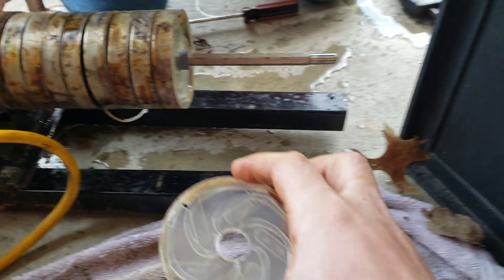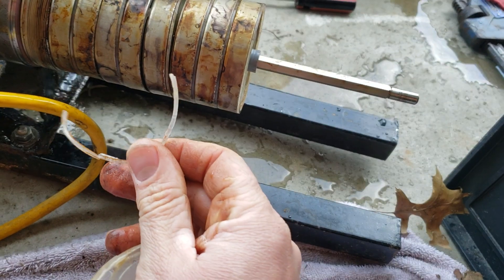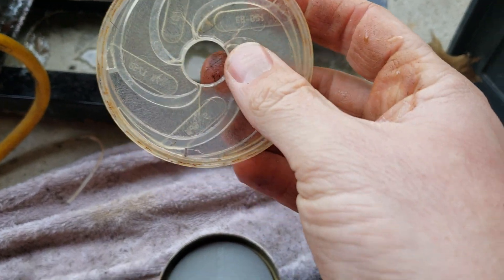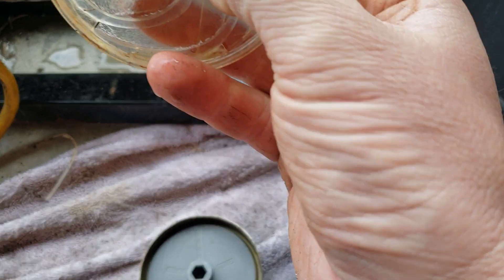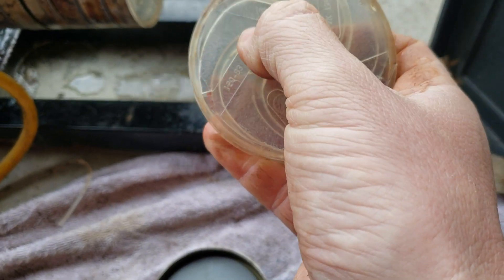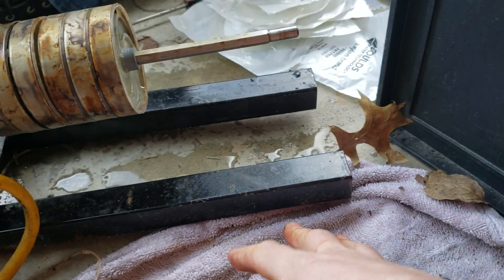All right, so we're just taking it all apart. We can clearly see here one of the diffusers definitely is in bad shape — we've got a whole bunch more over there. We are going to do a partial swap on these while we're in here. This one is looking, as we call it, a little bit distressed — mainly seeing where it's starting to go right there, and it wants to split out from the inside. We also had a little bit of junk down here, so we'll junk that one.